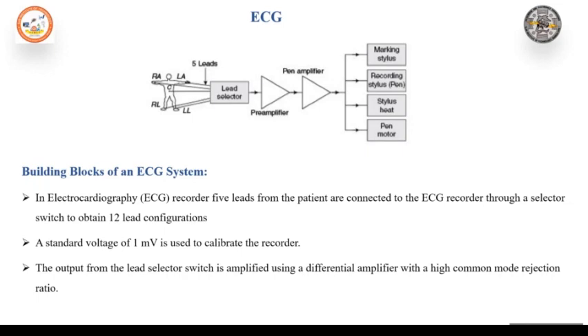The amplified output signal is picked up single-ended and is supplied to the power amplifier, which is usually of the push-pull differential type. The base of one input transistor of this amplifier is driven by the pre-amplified unsymmetrical signal, whereas the base of the other is driven by the feedback signal resulting from the pen position and connected via a frequency selective network. The output of the power amplifier is single-ended and fed to the pen motor, which deflects the writing arm on the paper. A direct writing recorder is usually adequate, as the ECG signal of interest has limited bandwidth.